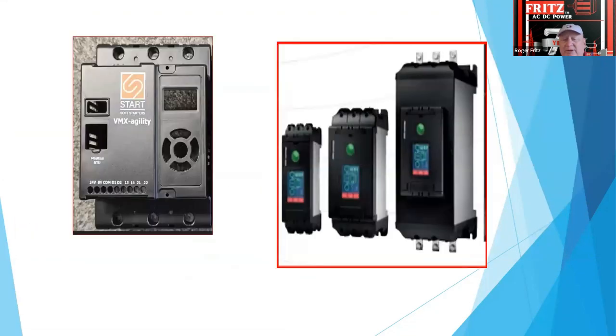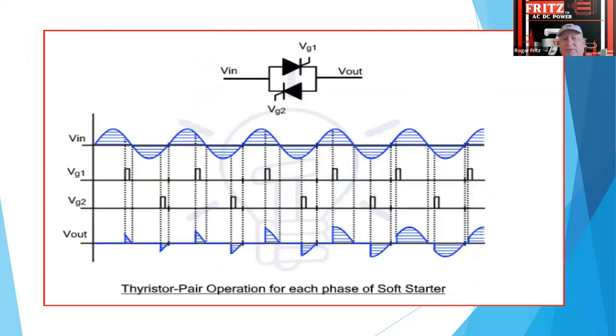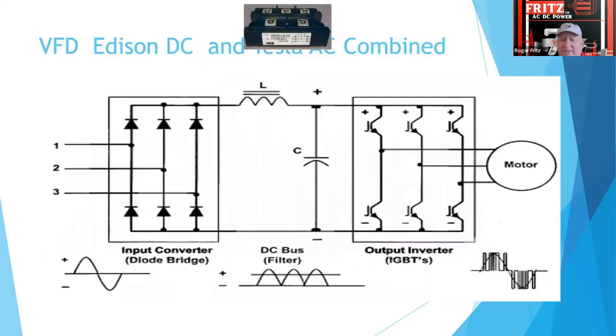But again, if you're not aware of what we're putting into the circuit, when we first put machines on in the 90s for Milton Bradley Toys in Massachusetts, we installed about 70 of them. We learned a lot real quick, because that hadn't been done before. With all of this pulsing, we had to come back and do what they call a harmonic study, and we had to determine how all those circuits came out. It was like probably back to college days of the resonant circuits that you create. So it's all controllable, but it's important to be aware of it when you do install something of any number of controls.